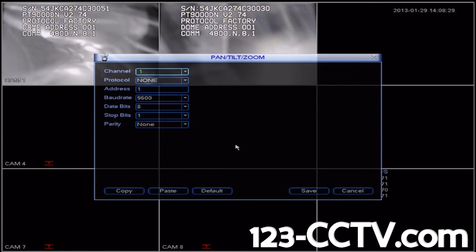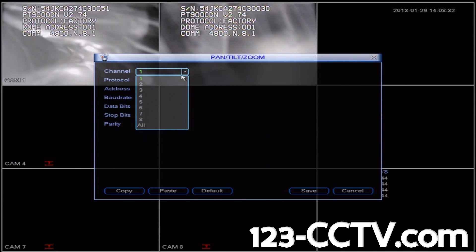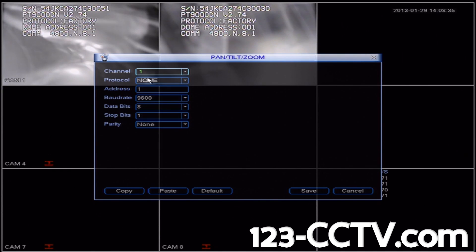You can see that we have various options, such as Channel, Protocol, Address, Baud Rate, Databits, Stop Bits, and Parity. We're going to configure Camera 1's settings, so we'll select Channel 1. Then we'll refer back to the camera's user manual to find which protocol and baud rate we need to use for this camera.